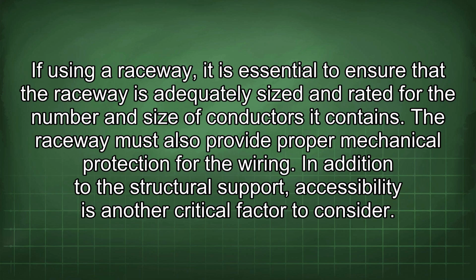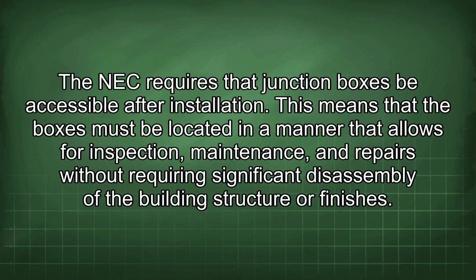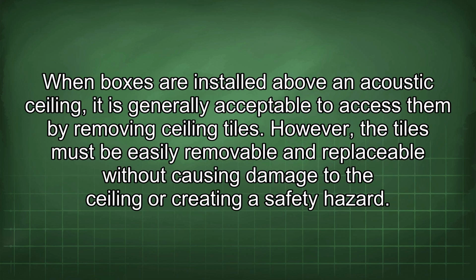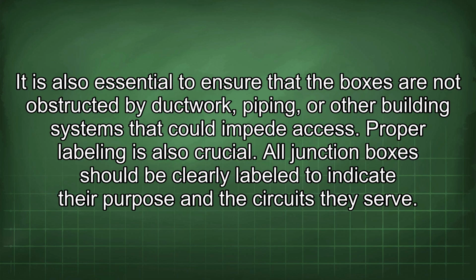In addition to the structural support, accessibility is another critical factor to consider. The NEC requires that junction boxes be accessible after installation. This means that the boxes must be located in a manner that allows for inspection, maintenance, and repairs without requiring significant disassembly of the building structure or finishes. When boxes are installed above an acoustic ceiling, it is generally acceptable to access them by removing ceiling tiles. However, the tiles must be easily removable and replaceable without causing damage to the ceiling or creating a safety hazard. It is also essential to ensure that the boxes are not obstructed by ductwork, piping, or other building systems that could impede access.